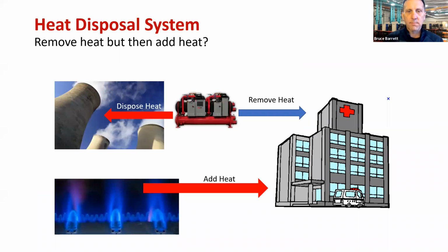Well, how would that look in a hospital? Well, we've got a boiler creating heat, adding it to the building, maybe to the perimeter of the building, maybe some of the core. We've got a chiller that is removing heat from the building, but also disposing that heat via a cooling tower. We'd like to close that loop. Instead of adding dollars to the boiler, adding money, energy to the boiler, and also throwing heat out of the tower, we want to reclaim that. We don't want to throw it away.